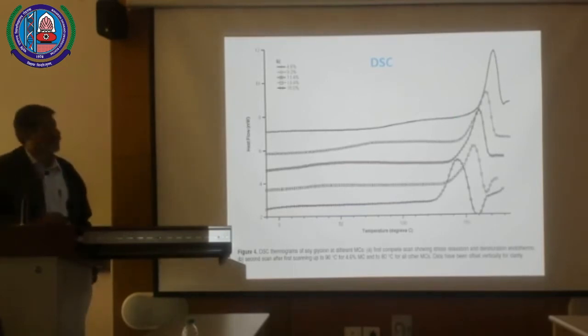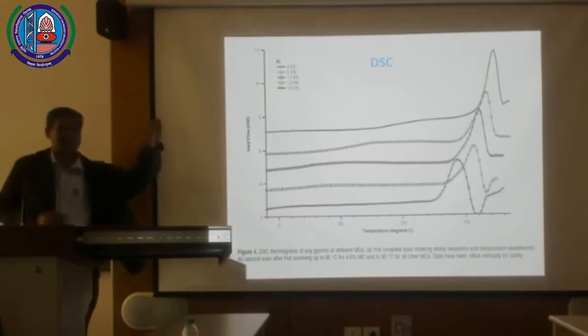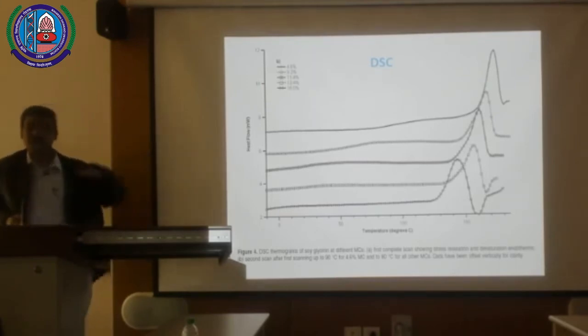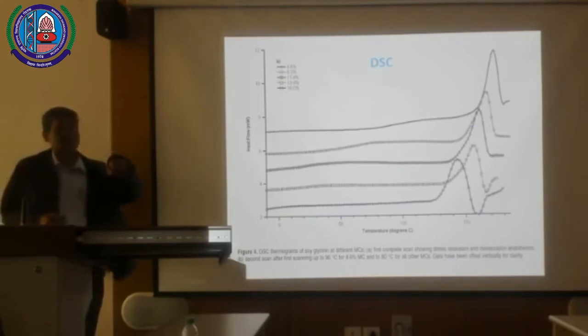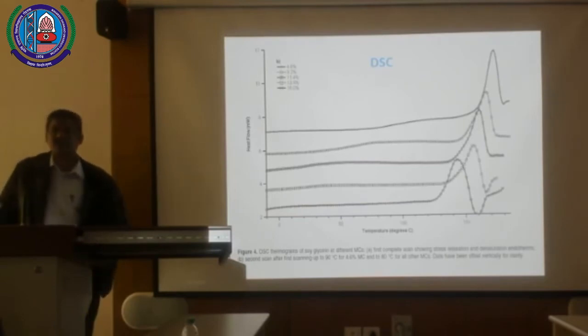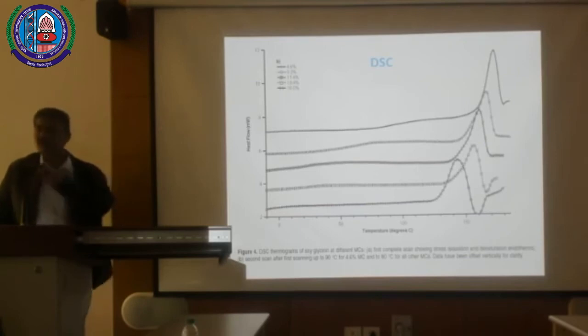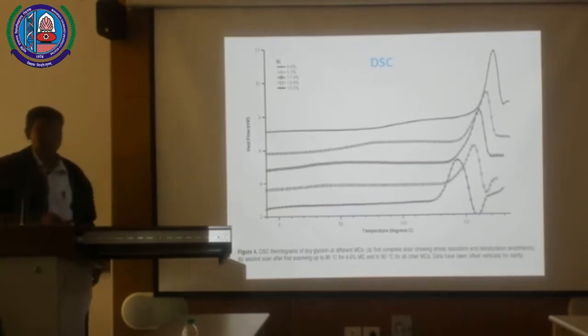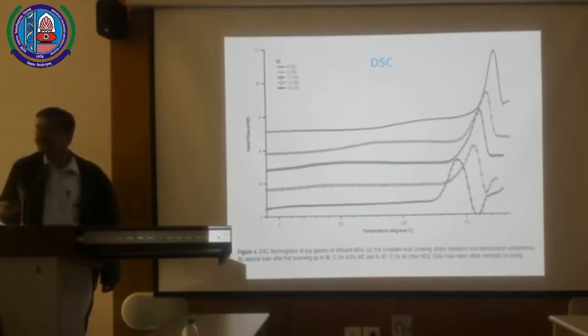The onset temperature is where the reaction starts, and when it ends, that's the end. The midpoint of the inflection point is known as the glass transition. So basically, you take two data points and compare throughout the scans: at what point my delta Cp crosses my threshold. As soon as it crosses, I mark that as the glass transition. Usually the midpoint of this, the inflection point, is the glass transition. Is this clear now, everybody?